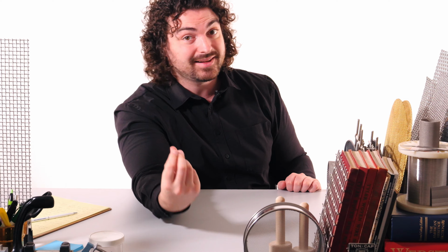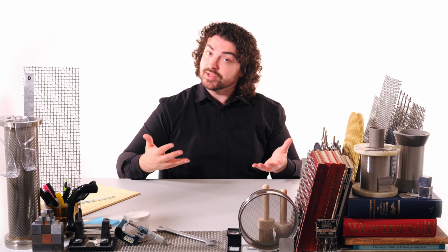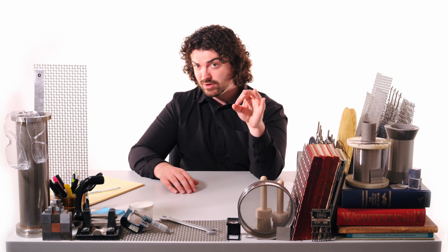Corrosion directly impacts system performance. For example, scaling and corrosion on heat exchanger surfaces reduces thermal efficiency, increasing your energy consumption by up to 15% per millimeter of scale. In reverse osmosis systems, corrosion of membrane housings and piping can lead to pressure drop, reduced permeate flow, and compromised water quality. These inefficiencies translate into higher operational costs, more frequent maintenance, and potential system shutdowns.